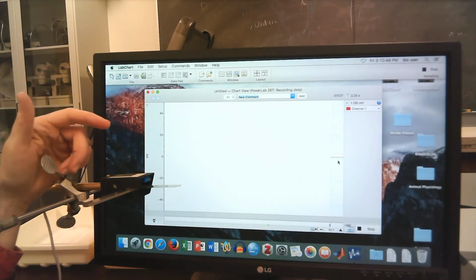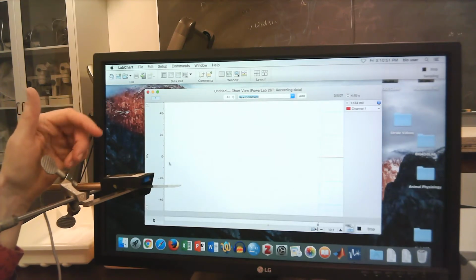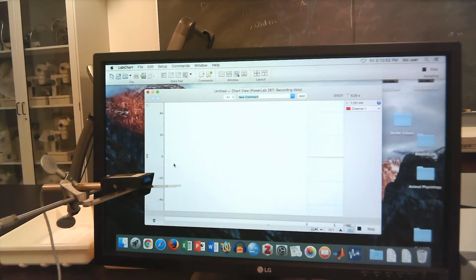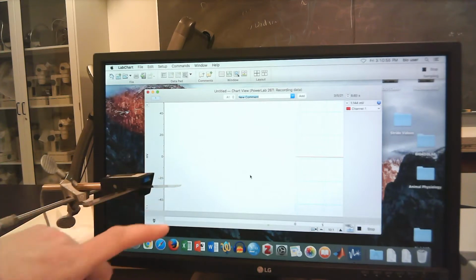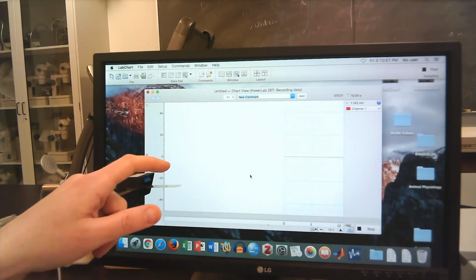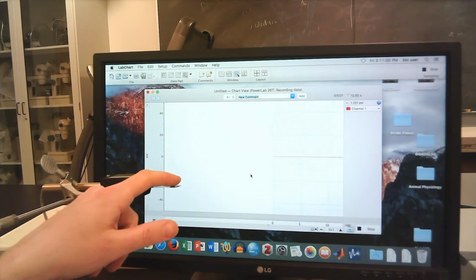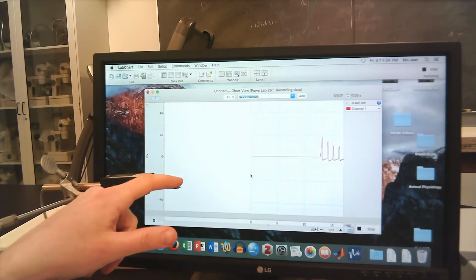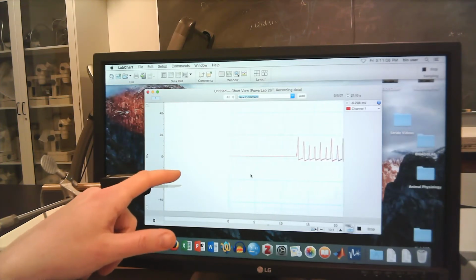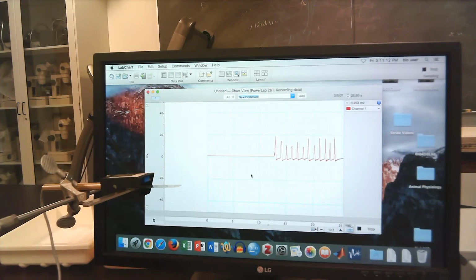Okay, so it's a slower sample rate, and it's actually automatically rescaled my axes. And now let's just watch as I tap the tip of the transducer. All right, so it's detecting changes in force as I tap the tip of the transducer. I'm just doing that as a way to test the transducer, make sure that it's working as I expect it to.